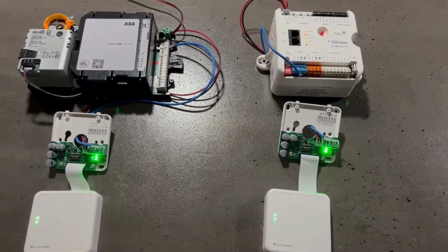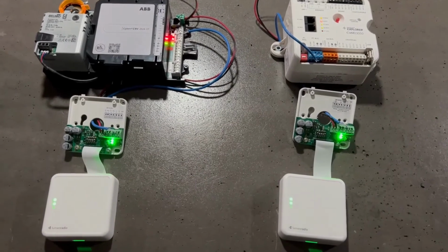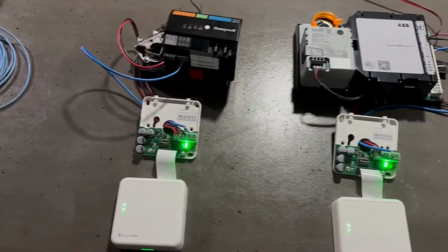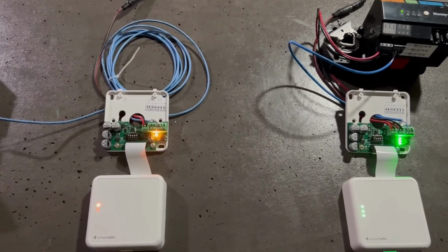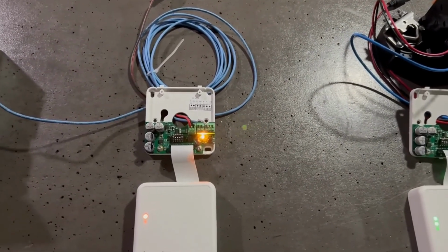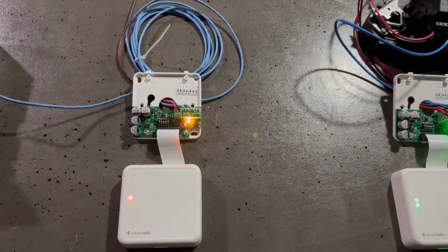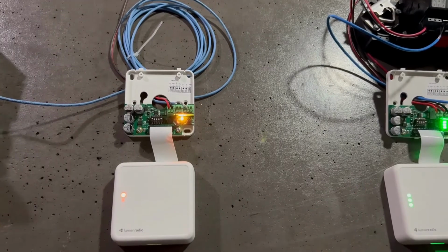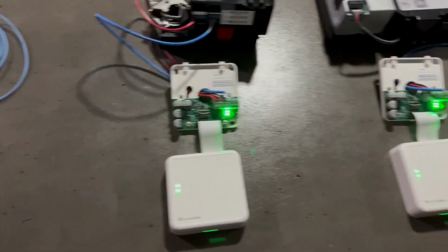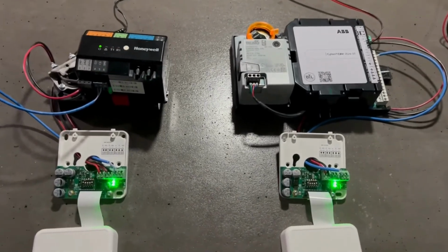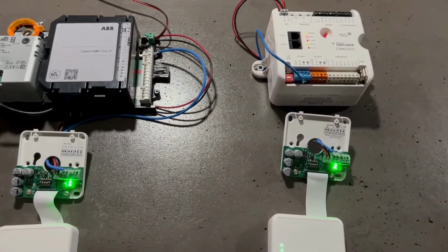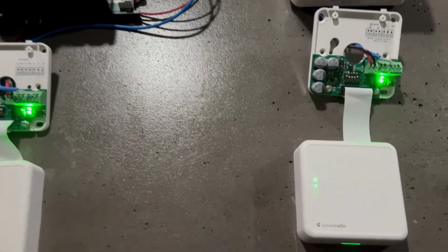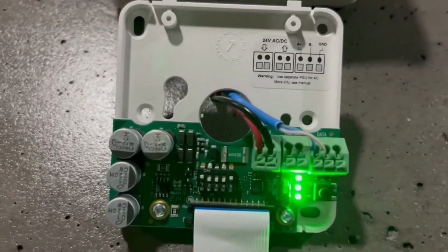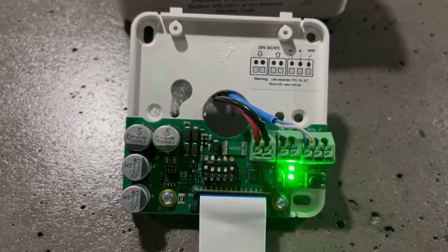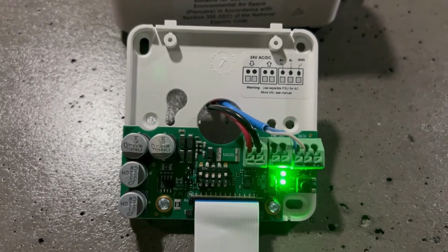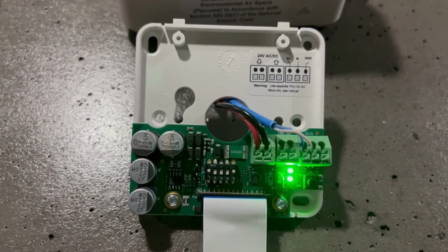Okay, on the bench today I have 4 W-BACnet devices, and I've got one set up as the gateway, and it's signified by the top LED glowing amber, signifying it is a gateway. And I've got 3 others, each with a different BACnet MSTP controller by various manufacturers. And I left the covers off the W-BACnet so we can see how the settings are set up in there. And you can see the dip switches are set for 38.4 and to get its baud rate from the node.